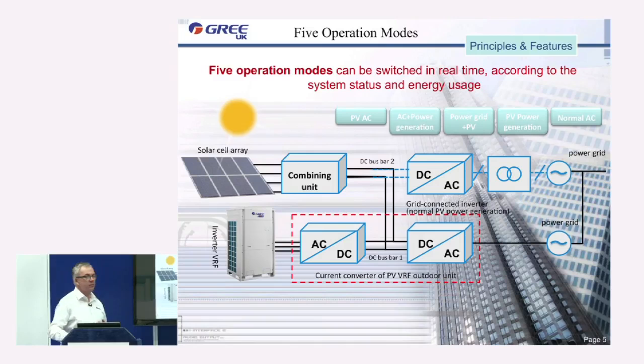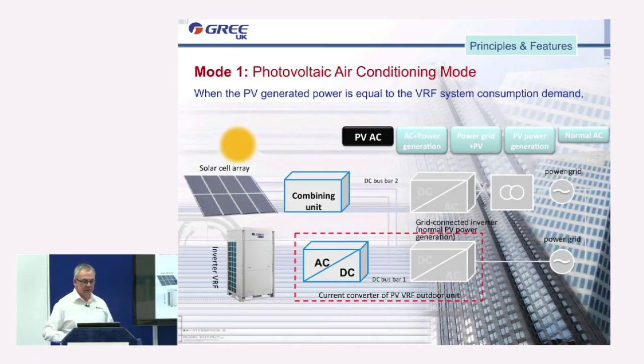So let me explain a little bit about the actual unit itself in terms of how it utilises the DC voltage and turns it into useful power. There are basically 5 modes of operation for the system. The first mode, in a perfect world, is when we are generating all the power that we need to run the PV VRF system. So if we have enough sunlight, we have a large enough solar cell array, we can use all the power generated to operate our system. We'll speak a little bit later about how much power we actually need for an average system, although an average system is not really something we can talk about very much because they vary dramatically.